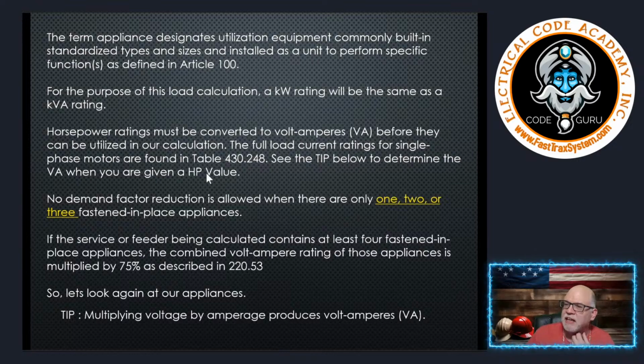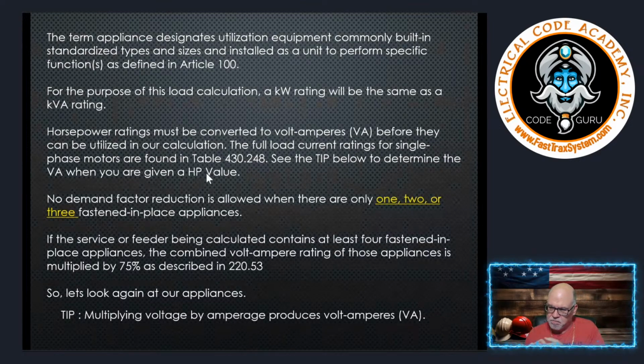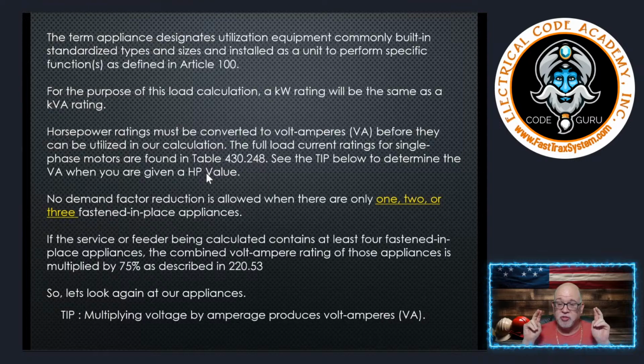Okay, now the first thing that we also want to remember is that typically in residential calculations like this, anything with a HP or horsepower rating is a motor. But a trash compactor, dishwasher, things like that, we're not considering those as motors. And that's important later when we're looking for the largest motor in the dwelling. So make sure that when you go looking for the largest motor later, you definitely look for a true motor.